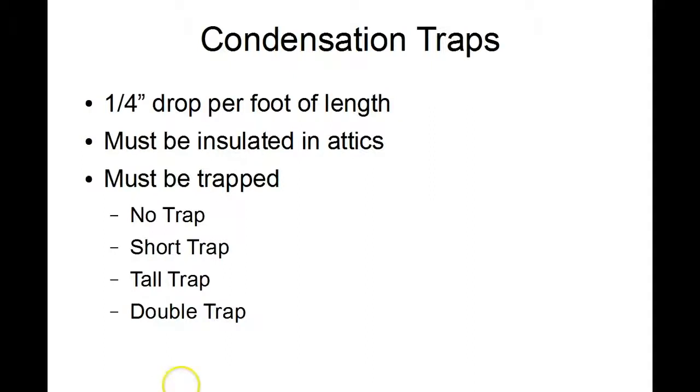Some things you need to know, and this is in most manufacturer's installation guidelines, is you need a quarter inch of drop per foot of length of condensation pipe. So if you have 40 feet of condensation drain line, you need a 10 inch drop from the outlet to the drain. That's something to keep in mind when you're routing drain lines, especially through the attic in a home where you don't have a lot of drop or if it's in a crawl space.